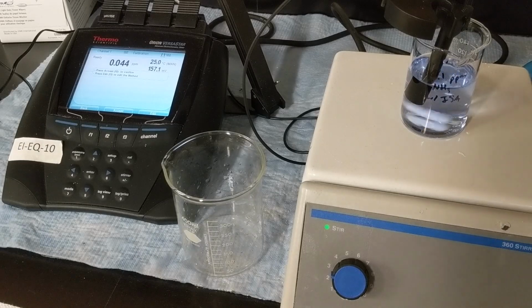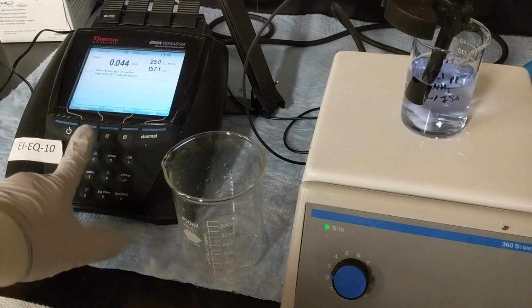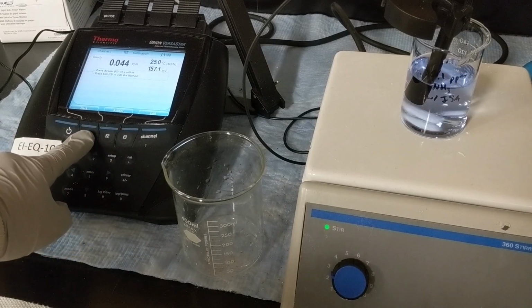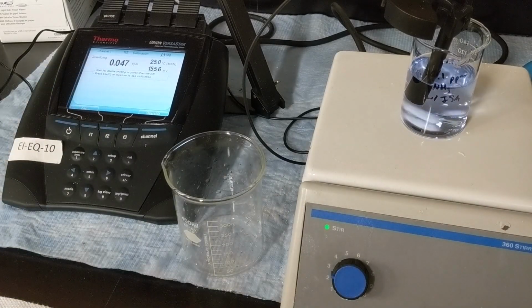Okay, so it has been a few minutes and the screen readout finally stopped at 0.044. Our protocol on this apparatus is we want to keep measuring until it gives us the same measurement twice in a row. And that's just because it takes so long to equilibrate that the software on the instrument thinks it's done before it's done. So instead of hitting accept or edit, I'm going to hit F1 to retry this. And then if we look at that, see it jumped from 0.044 to 0.047. And so I'm going to keep doing that until it gives me the same reading twice in a row. It should take a little while.